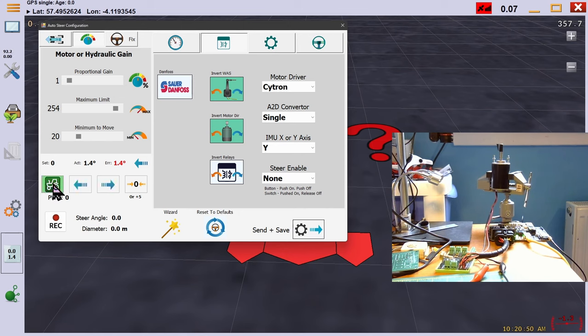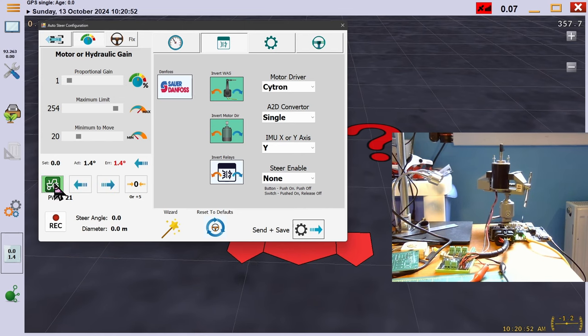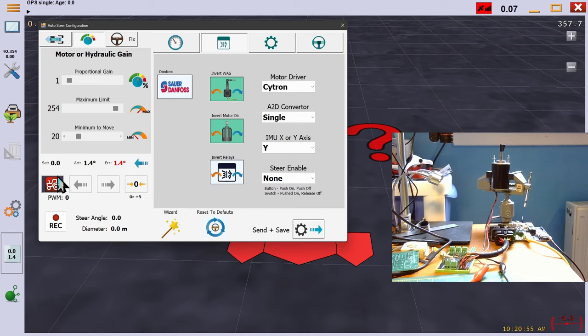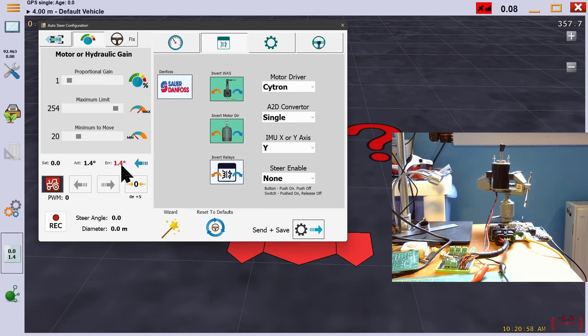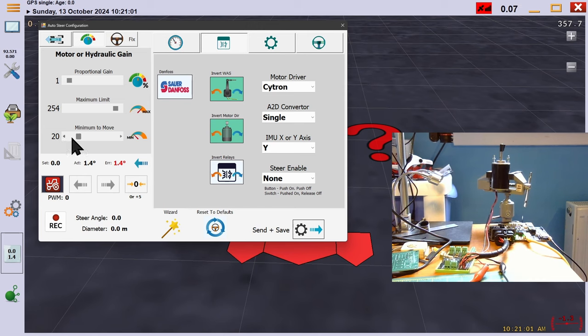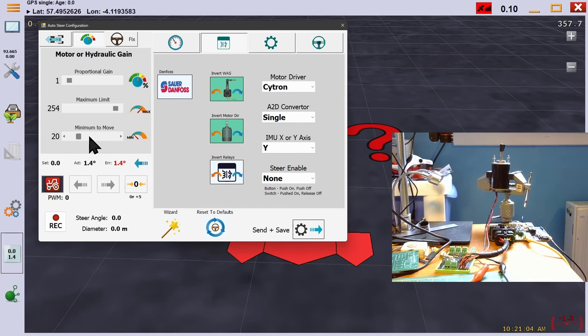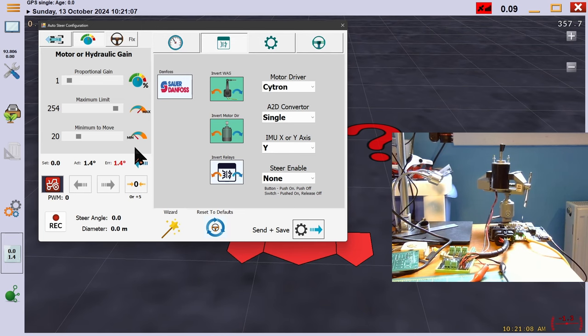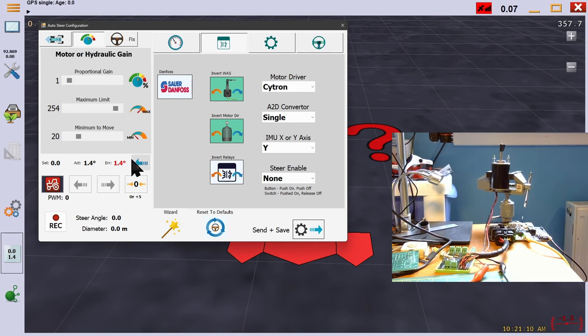Minimum PWM should be set to a value just below that which makes the motor start to turn or the valve start to open. To work out this figure, we set proportional to 1 so the multiplier is negated. Please note that your tractor should be moving while you set this, as it's easier to turn the steering when moving than when sat still. Find a clear open space and be mindful of your environment.